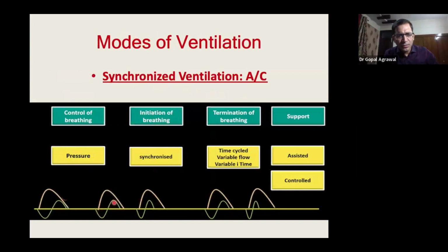So this is a spontaneous breath, and this is the machine's breath. All the breaths initiated by the baby will be supported by the machine and synchronized with the machine. If the baby is breathing well, all the breaths will be supported, unlike SIMV where only some breaths will be supported. If the baby is not breathing, it will go into a control mode.